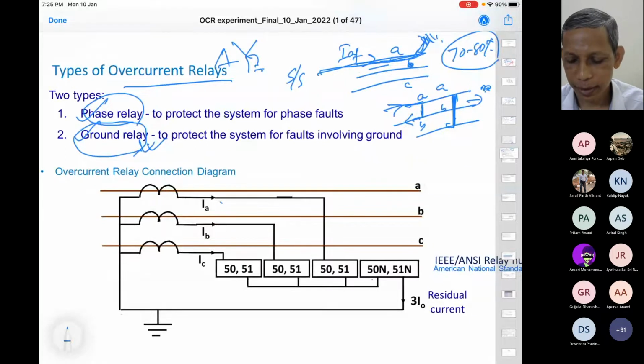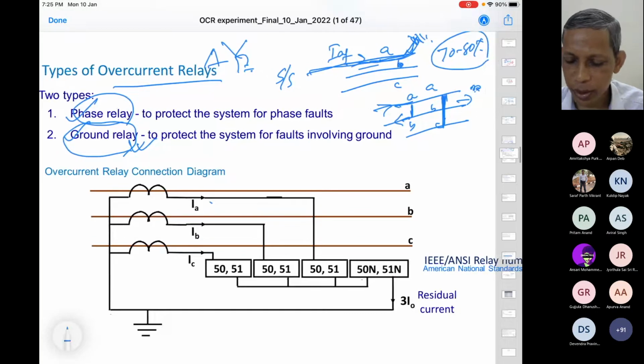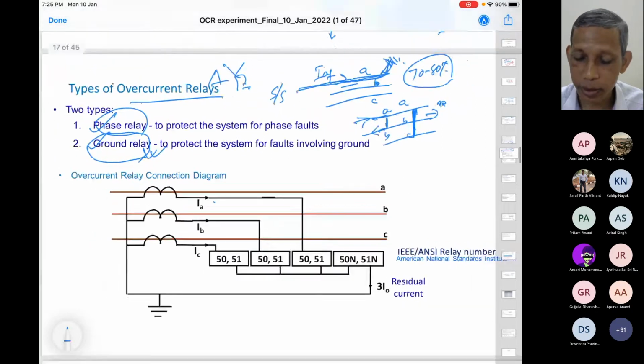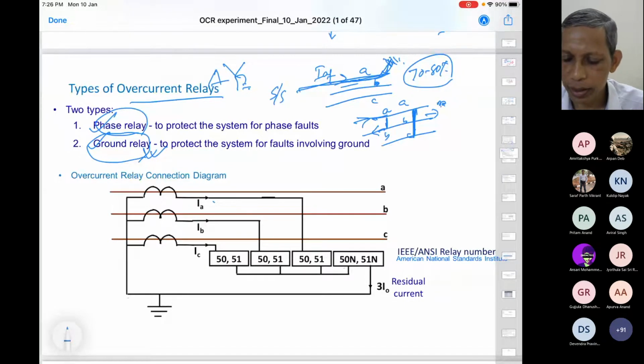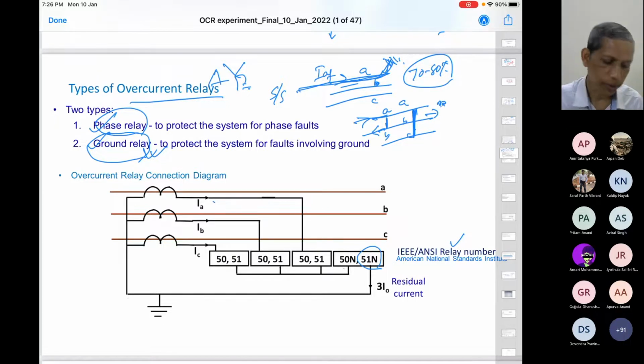And I will put different numbers there, 50, 51 and so on. In numerical relay terminology we use IEEE and ANSI, the American National Standards Institute, relay numbers. Power system engineers know what is 50, what is 51, and also the ground relay and the one for neutral. And 50 versus 51: 50 is for instantaneous, and 51 is with time. We call it inverse definite minimum time. They have time information, but 50 is instantaneous.